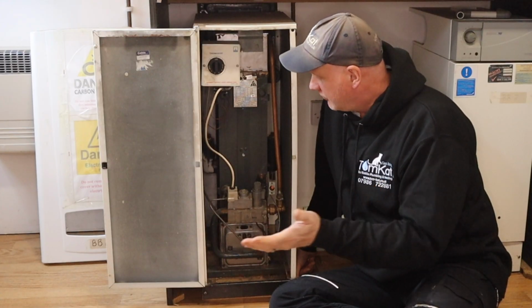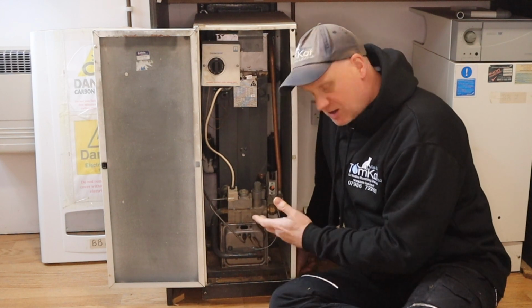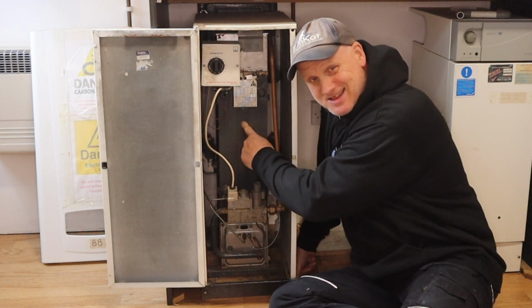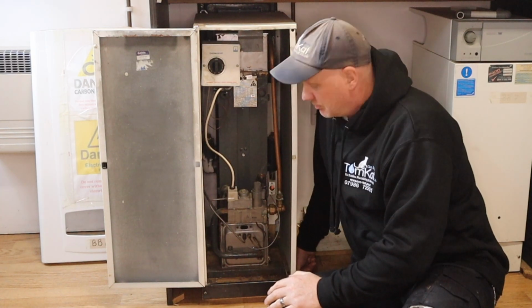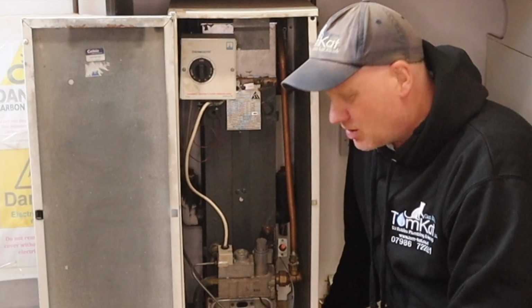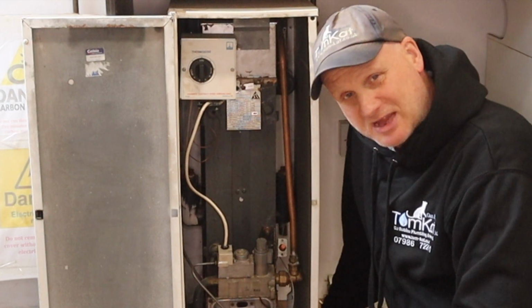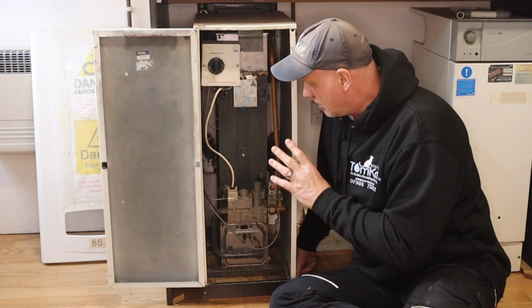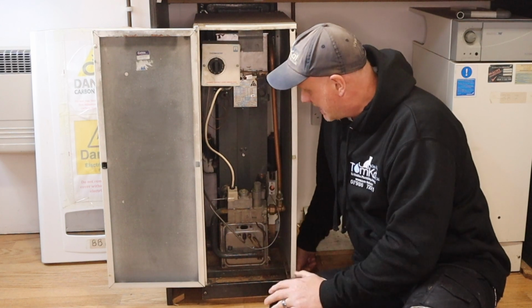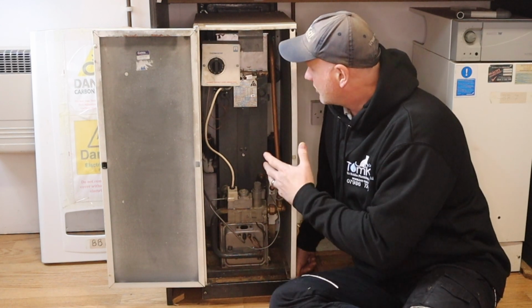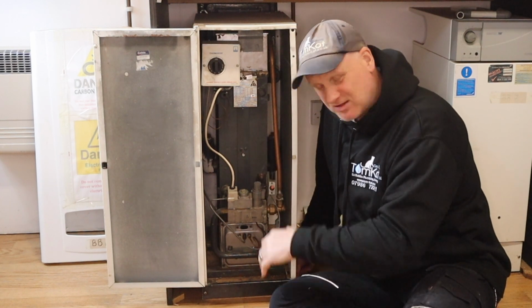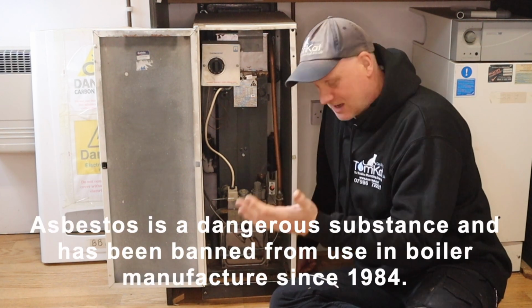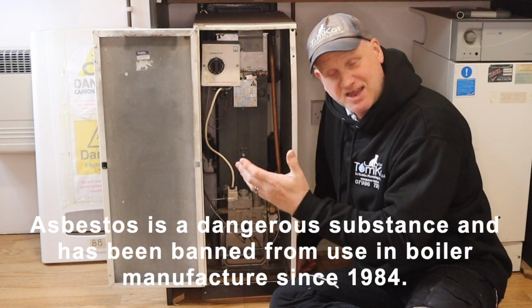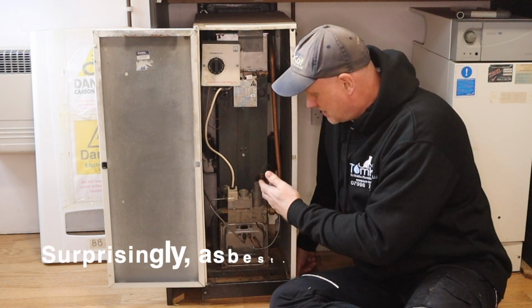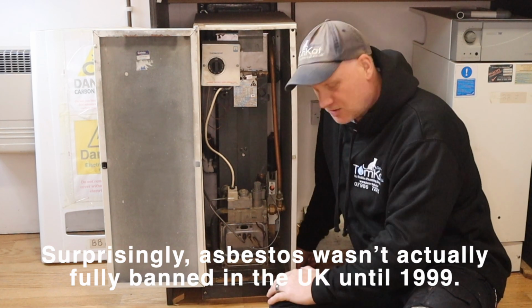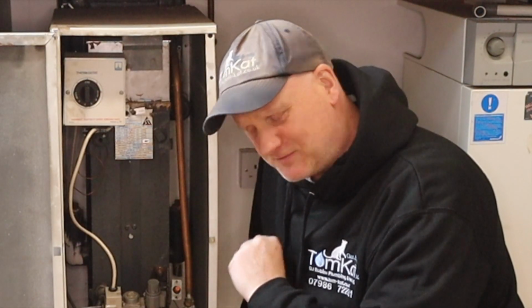boilers running. Now, if your boiler looks like this one, which is an old floor standing cast iron heat exchanger balance flue regular boiler, then it probably will be more cost effective for you to replace this old beast than trying to keep it running. Now, a lot of the spare parts for this boiler now are obsolete, and also a lot of these old boilers have asbestos in them, especially in the seals and the protection from heat. Gas engineers are not allowed to work on these because of the asbestos content. Just bear that in mind first.